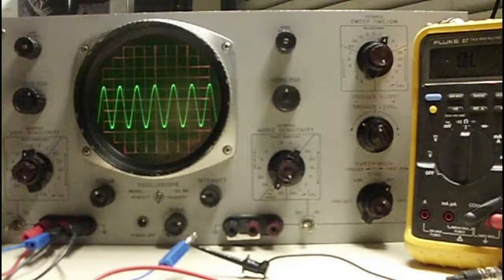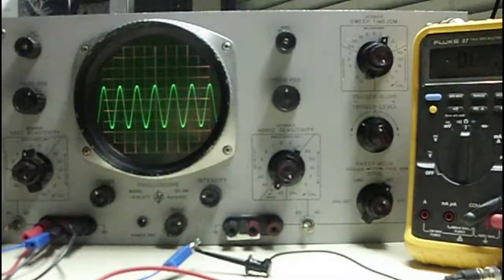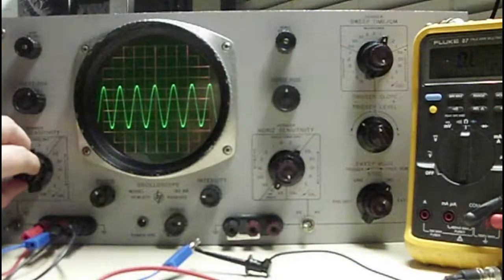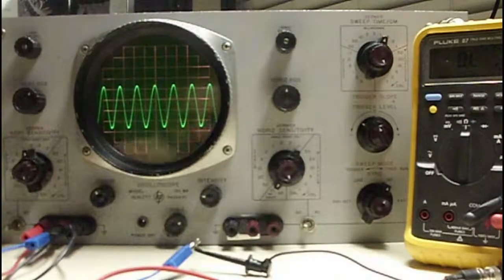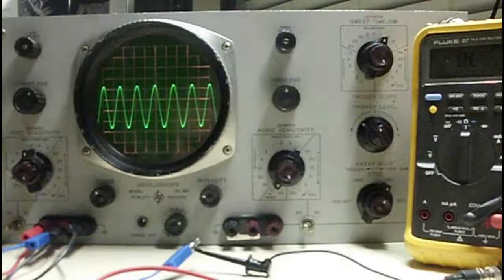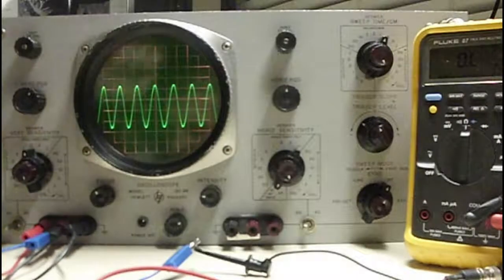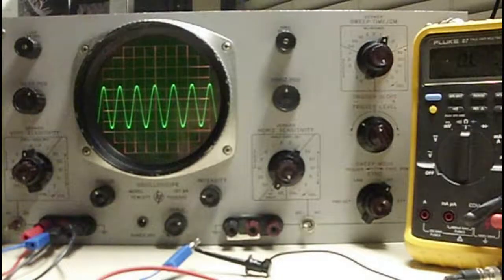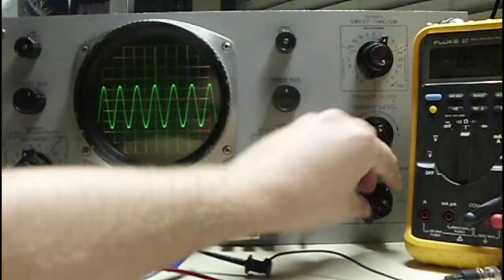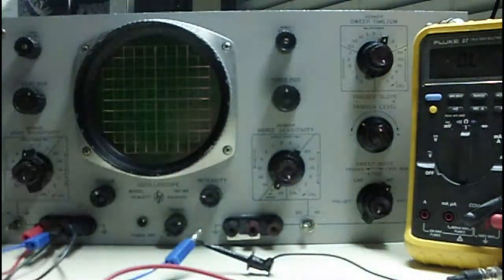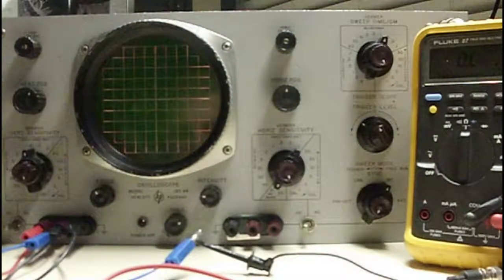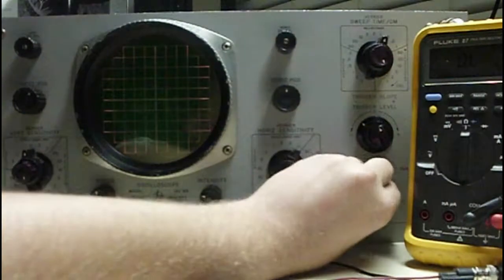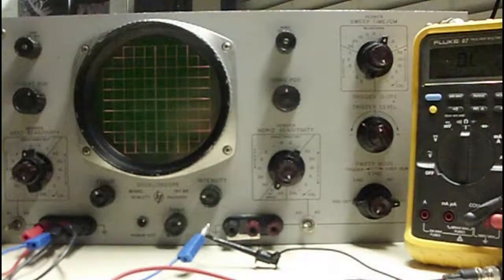Horizontal sense to internal sweep X1, so that's there. Obviously the vernier should be in calibration for everything here. Sweep time to 1 millisecond per division, we got that. Sweep mode to preset, and then it says set sync to external with no input. So I don't quite know what that means, but we'll go ahead and set it on external with no input.